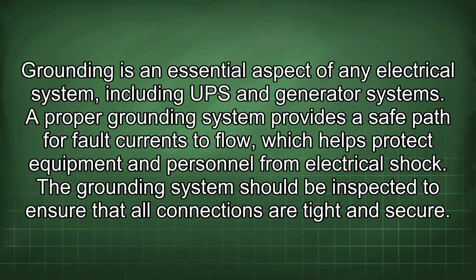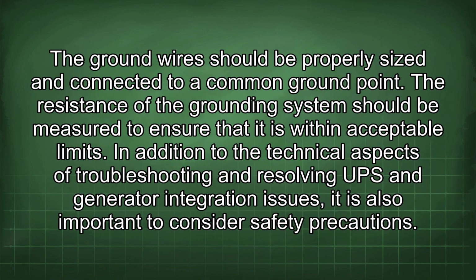Grounding is an essential aspect of any electrical system, including UPS and generator systems. A proper grounding system provides a safe path for fault currents to flow, which helps protect equipment and personnel from electrical shock. The grounding system should be inspected to ensure that all connections are tight and secure. The ground wires should be properly sized and connected to a common ground point. The resistance of the grounding system should be measured to ensure that it is within acceptable limits.